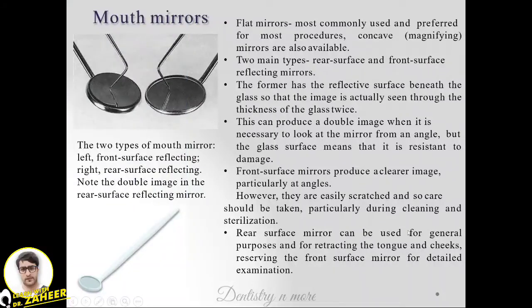The rear surface can produce a double image when it is necessary to look at the mirror from an angle, but the glass surface means it is resistant to damage. Front surface mirrors produce a clearer image, particularly at angles, but they are easily scratched, so care should be taken during cleaning and sterilization. The rear surface mirrors can be used for general purposes and for retracting the tongue and cheeks.